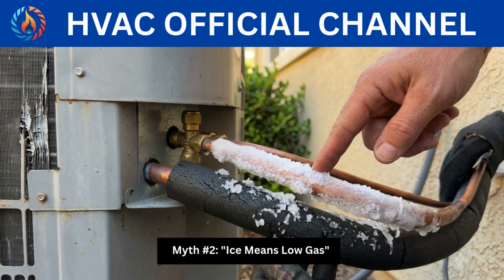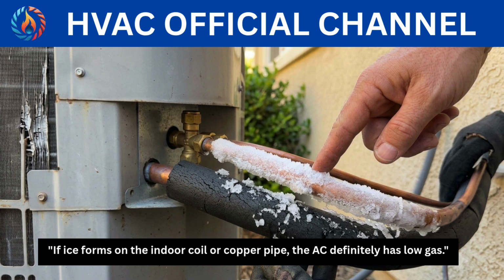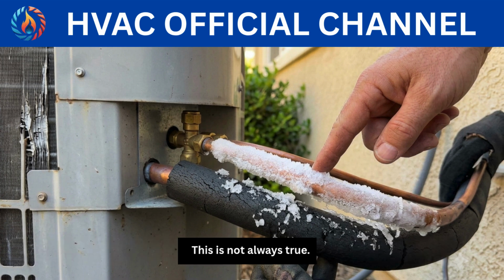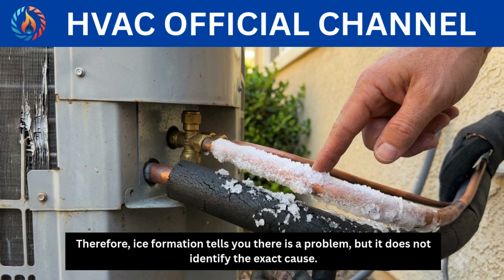Myth number 2. Ice means low gas. Another common belief is, if ice forms on the indoor coil or copper pipe, the AC definitely has low gas. This is not always true. Ice can form because of dirty air filters, blocked airflow, a faulty indoor blower fan, a dirty evaporator coil, low refrigerant caused by a leak, or a malfunctioning expansion device. Therefore, ice formation tells you there is a problem, but it does not identify the exact cause.